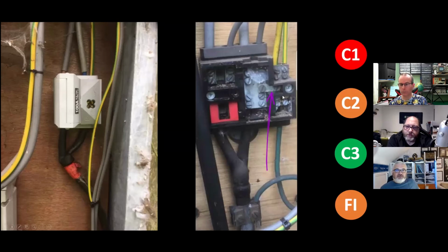These will be quite familiar to a lot of people. I think it's fair to say there's a good few million of these. Where so with this lid on to the electrician, yes. This looks like a TNS. Yes. Because you've got that braid there. But when you take it off, you can see there's that link. So it's a PME.